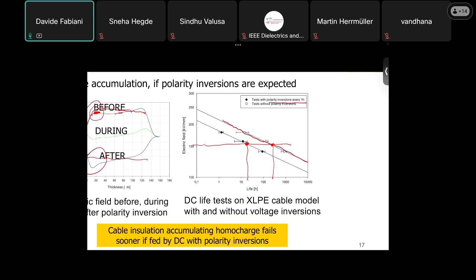So homocharge can be tolerated if you do not have polarity reversal in your cable, but if you have polarity reversal on your cable, please, you must have a really negligible amount of charge accumulated in the cable itself, okay? So also homocharge cannot be tolerated. So how can we reduce the charge? If you remember, at the beginning, I told you that many years ago, the design field of HVDC cable was lower than 10 kilovolt per millimeter, because 10 kilovolt per millimeter was the threshold for space charge accumulation, okay? For XLPE, for instance, you can see that this threshold is about 11 or 12 kV per millimeter. So below that value, we do not expect to have space charge accumulation.